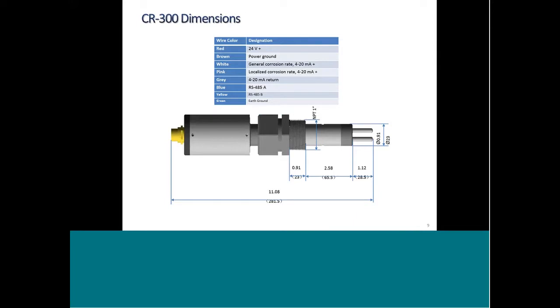Next slide is just some general dimensions, and I can pass this PowerPoint presentation along to anybody that may be interested in it. On the CR300, to give you some understanding, it does have 3 depth channels on the actual probe itself. There's an O-ring there, a locking mechanism to prevent it from blowing out, which you have to physically remove the O-ring, and on that shaft you can set the depth at 3 different levels, 1-inch, 2-inch, and 3-inch. And in our operation manual, we provide an installation guideline, but it's standard 1-inch NPT on the threading, the Kynar compression adapter connecting the probe itself.